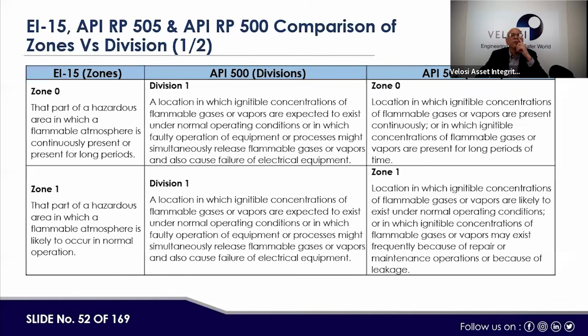After going through the basic definitions, which are the standards? The standards are IP-15 or EI-15, then API 505 or API 500. These standards are more important than IEC 60079 for electrical instrumentation apparatus or equipment. Also, IP or EI part 1 is for the selection of electrical and instrumentation equipment. Now, if we try to compare EI 15 zone 0 and zone 1, and also compare API, here also there is zone 0 and zone 1.